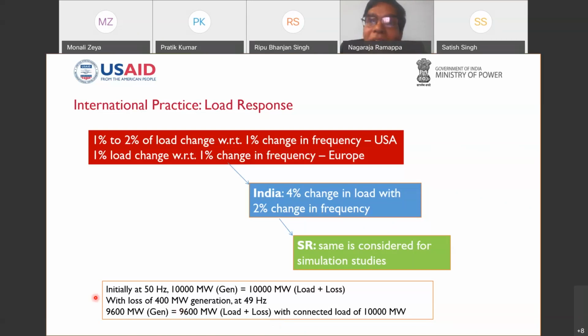Assume that we are operating with 10,000 megawatt generation and I am at 50 Hz. Load plus loss is equal to 10,000 megawatt. Now our load starts increasing. Assume that the load starts increasing or there is a loss of a generation of 400 megawatt.